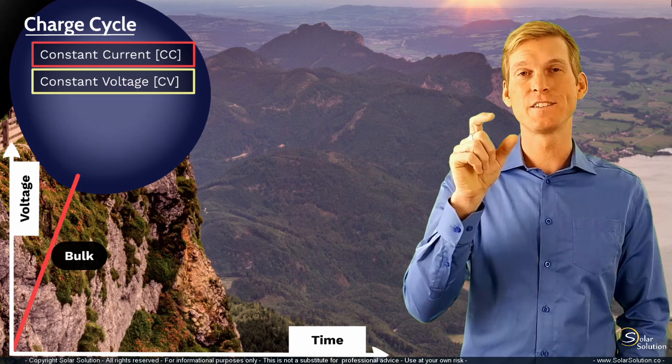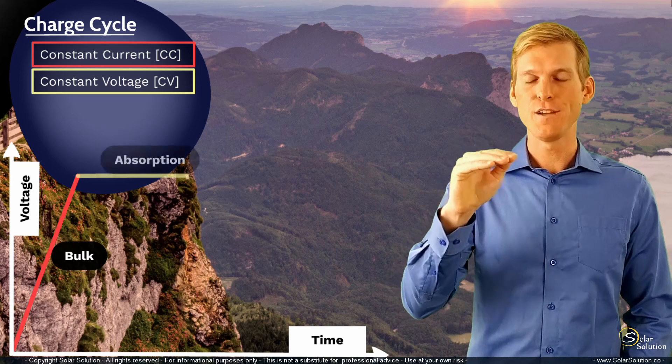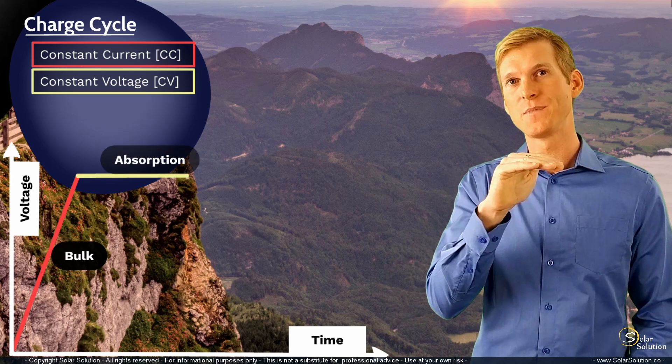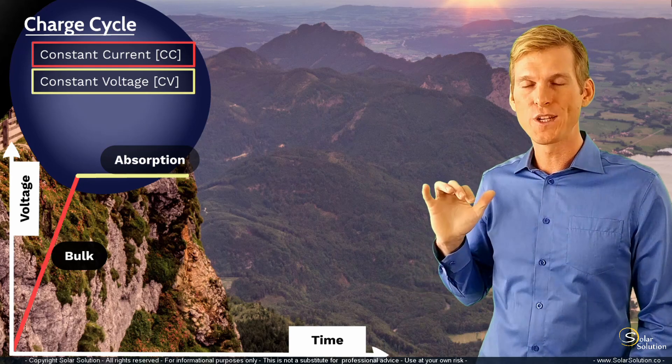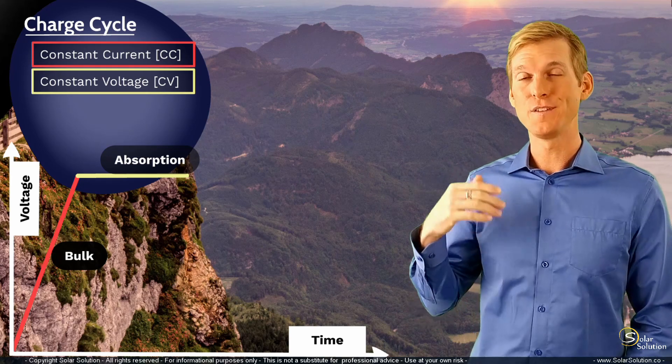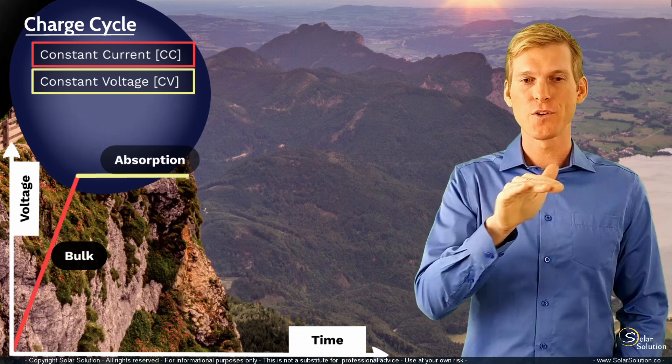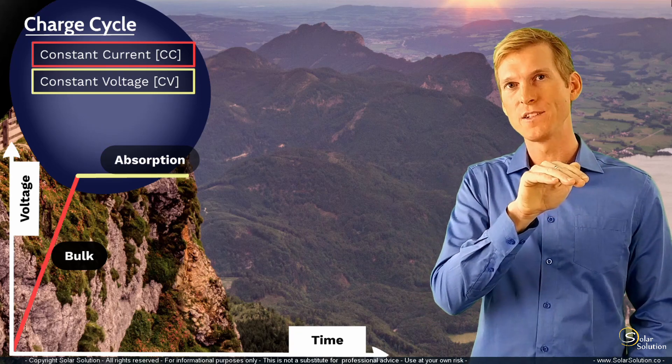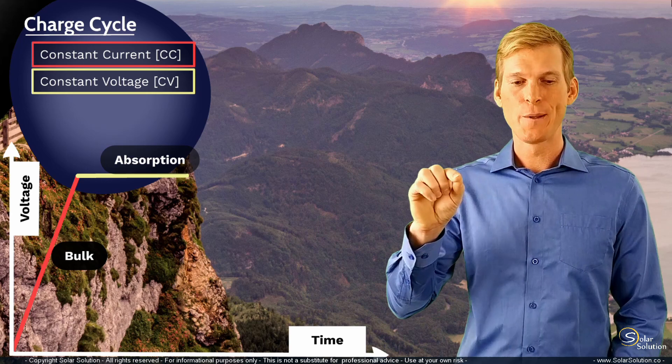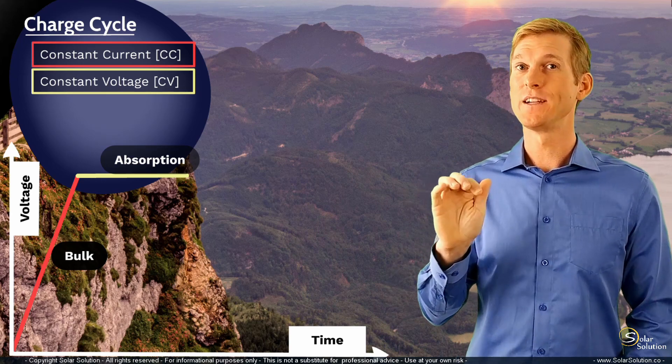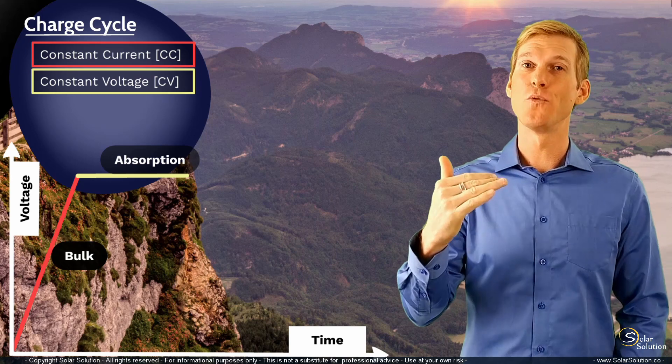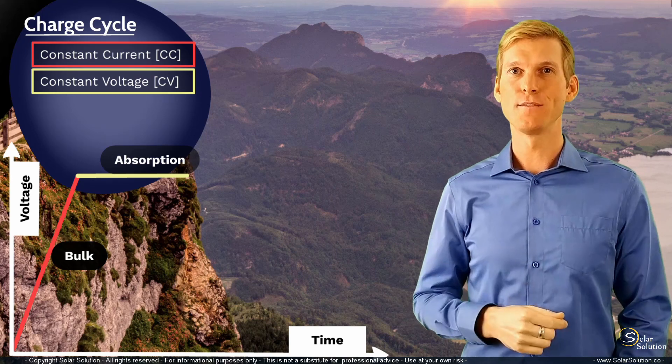Now just remember that in this stage, in the absorption stage, even though the voltage is kept steady, so the voltage remains at the same level, you are still pushing energy into the battery because you are feeding it with current. And also, as time progresses during the absorption stage, you will see that you have to add less and less current into the battery, so less and less energy in order to maintain this voltage level.